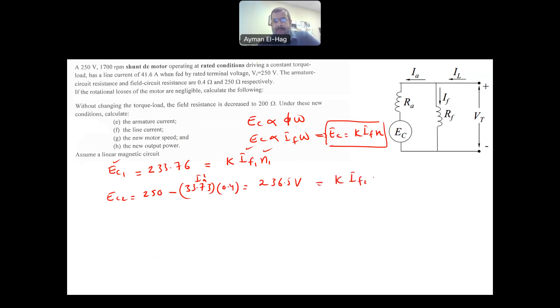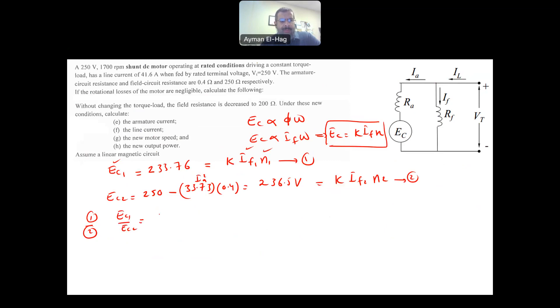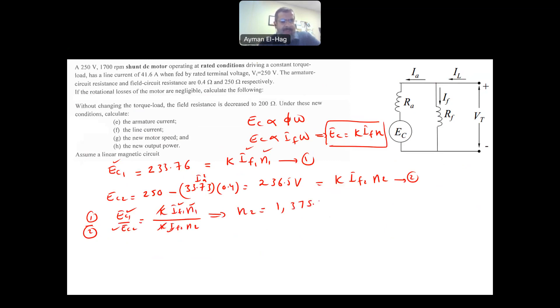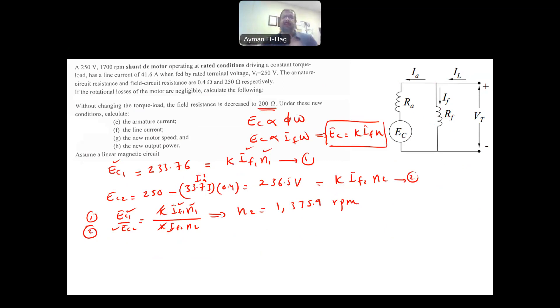Solving for N2: N2 = (EC2 × IF1 × N1) / (EC1 × IF2) = 1,375.9 RPM. When we reduce RF from 250 to 200 ohm, IF increases, which increases the flux, and in turn reduces the motor speed — and vice versa.